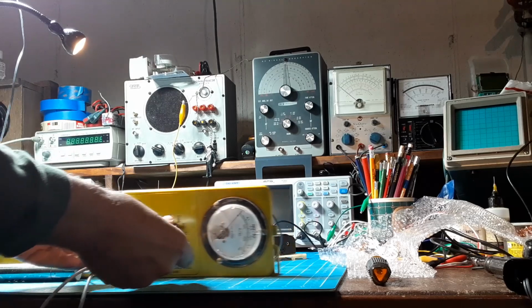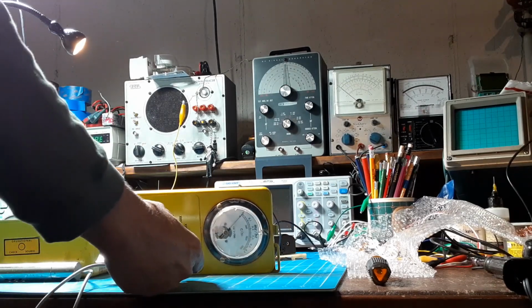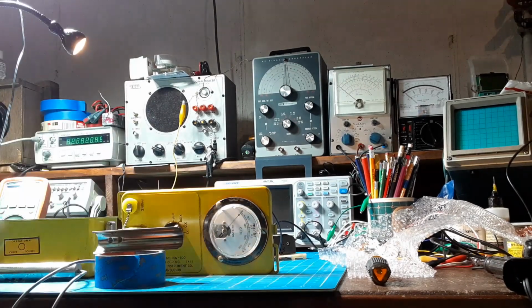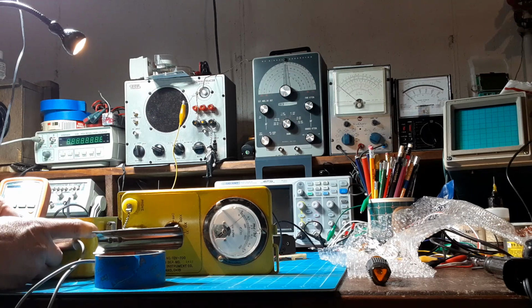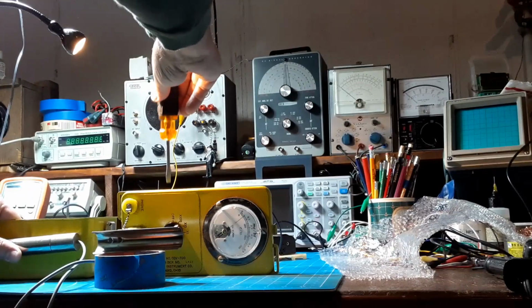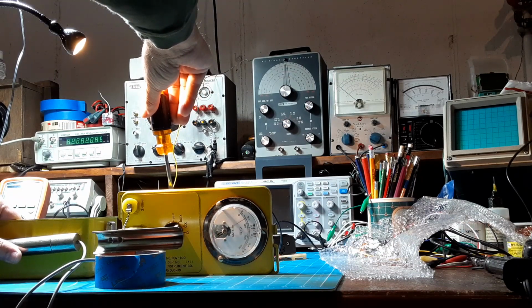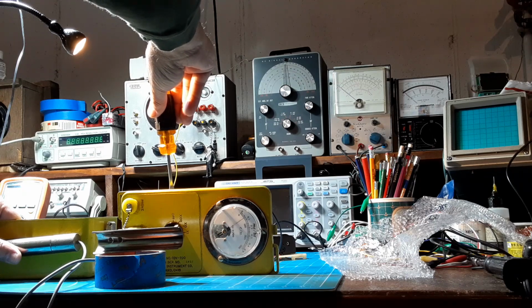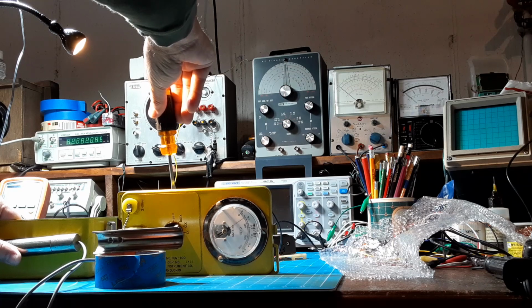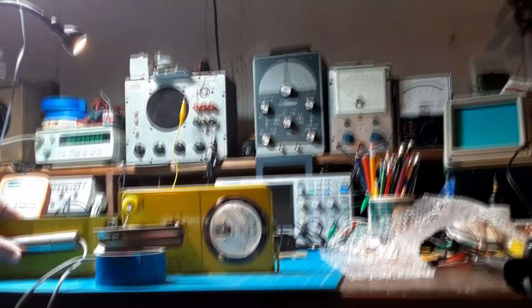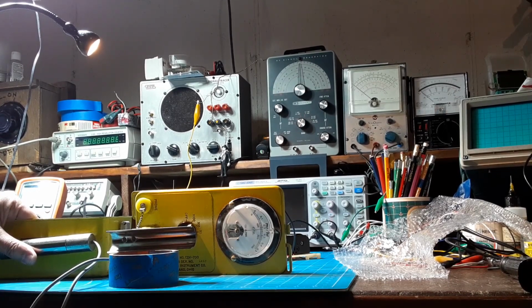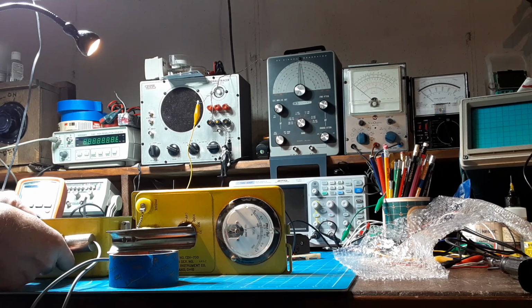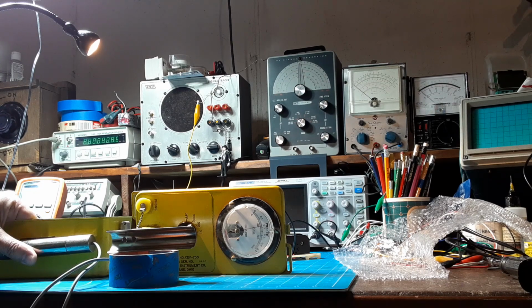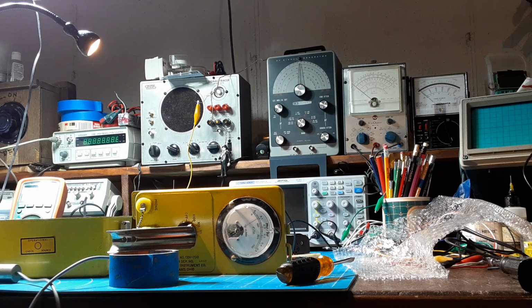Okay. I had that back there so it wouldn't tip over. Let's use that. Okay, well, let's see. I'm going to try to hold this here and do the calibration at the same time, which you shouldn't do at high voltage things, but get it at peak. Okay, that's peak there. Well, that ain't bad. That's about right. That's really good. So that's how you calibrate it. And so now it's accurate.